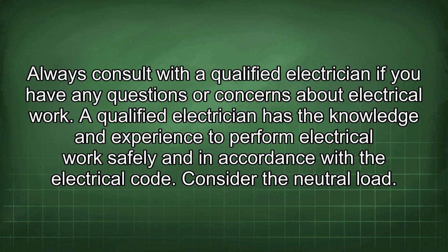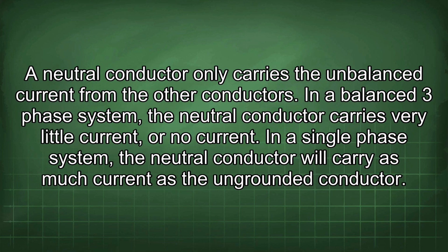Consider the neutral load. A neutral conductor only carries the unbalanced current from the other conductors. In a balanced three-phase system, the neutral conductor carries very little current or no current. In a single-phase system, the neutral conductor will carry as much current as the ungrounded conductor.